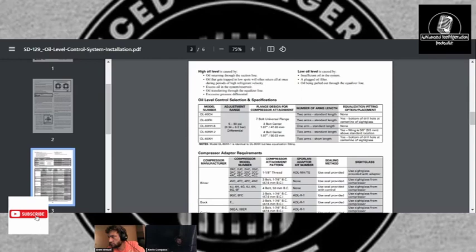Now, when you're doing a new store startup, or anytime I'm having a lot of oil feed issues on compressors or oil balancing issues, I'll reset all the floats at once. So I'll take all the floats, run them all the way in, and then back them out to whatever the OCV should be. So if after I check the OCV, say it's 20 pounds, I'll run all the floats out to where they need to be. And then I'll watch the rack and let it run for a while. If I've got ones that are filling up and I shut off the oil line and they stop filling up, I had a bad float. Especially on startup, if it's doing it, I'm just changing it out. It's a bad float. It's not holding its setting for where it is. It's just going to get changed out.